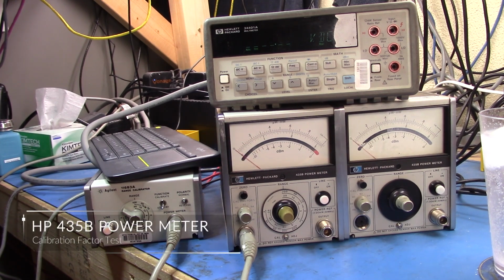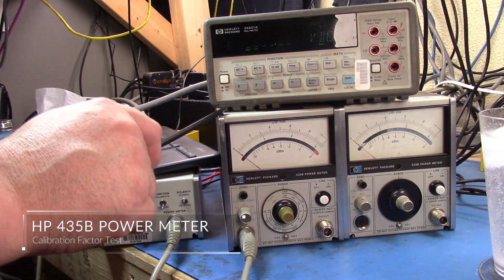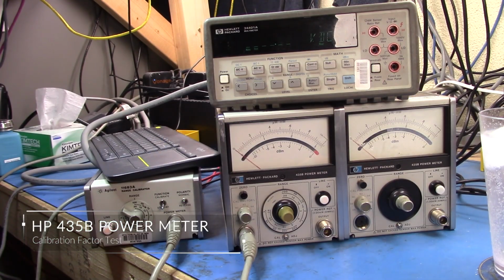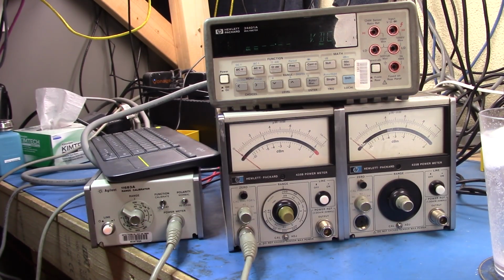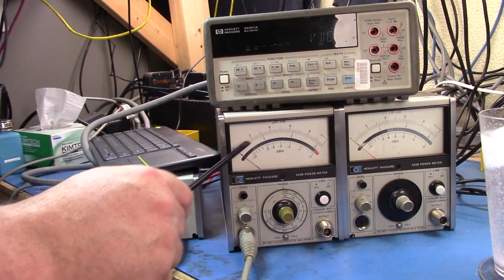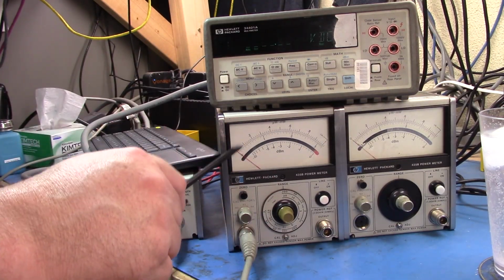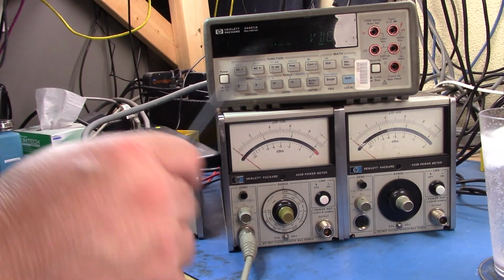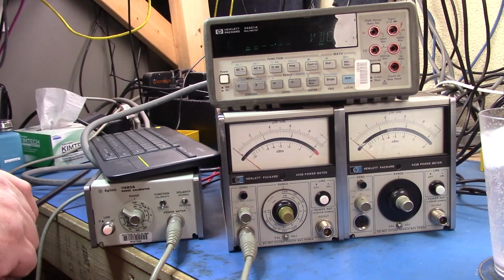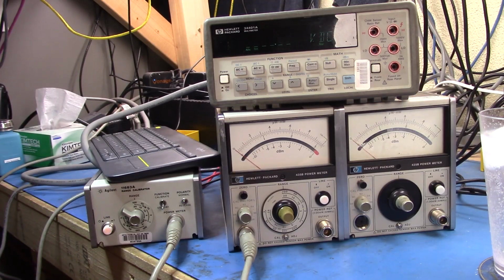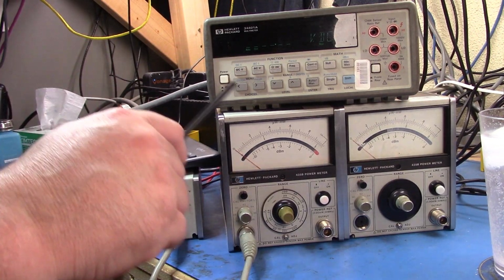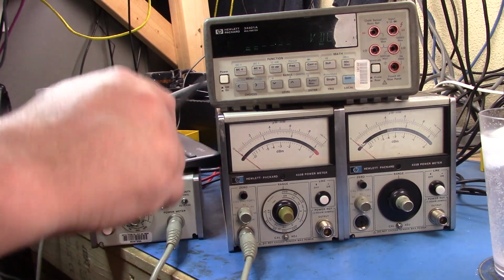Well, good afternoon. I just wanted to do the last step in calibrating or performance testing my HP 435B. In the previous videos, we've looked at the power reference, got that to be 1 milliwatt. We've looked at zero carryover and confirmed that we're within spec as we move from range to range. We've then used the 11683A to check that our range accuracy is correct.